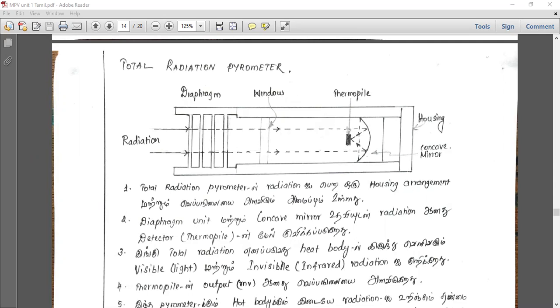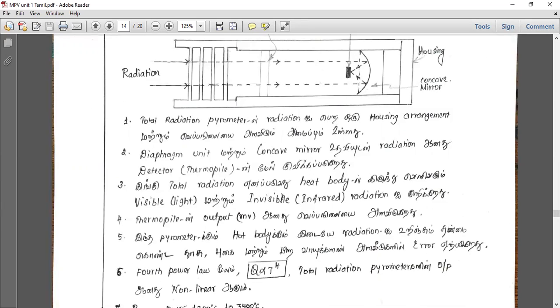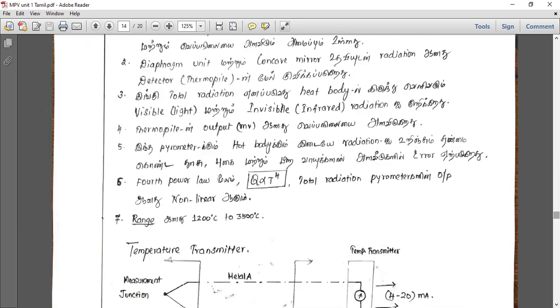The detector produces an equivalent EMF. The EMF is calibrated to temperature readings. This follows the fourth power law: Q is proportional to T to the power 4. The output is non-linear. The range is 1,200 to 3,500 degrees centigrade.